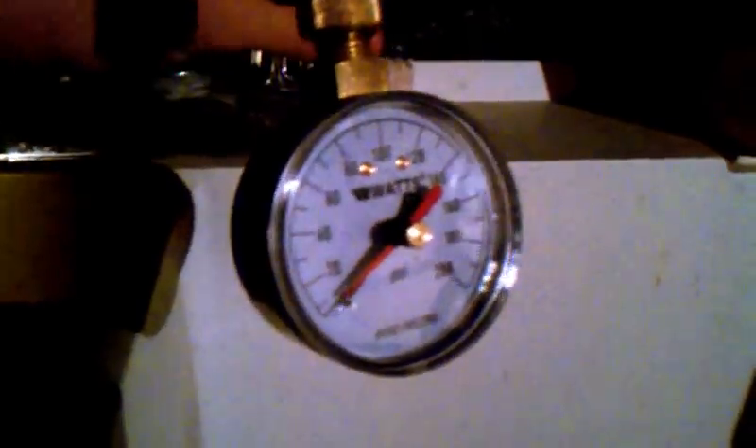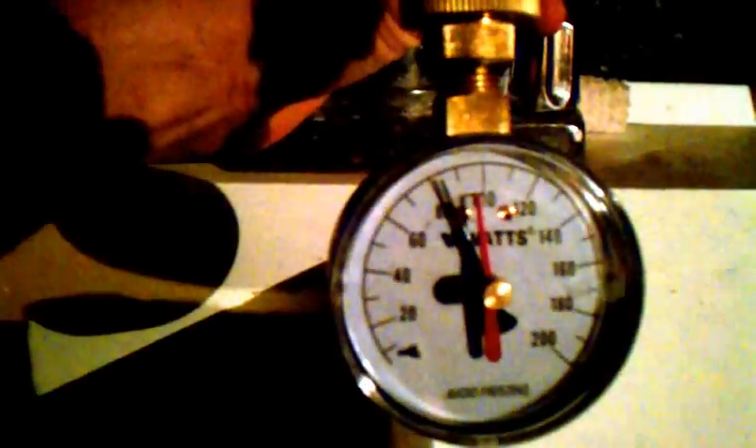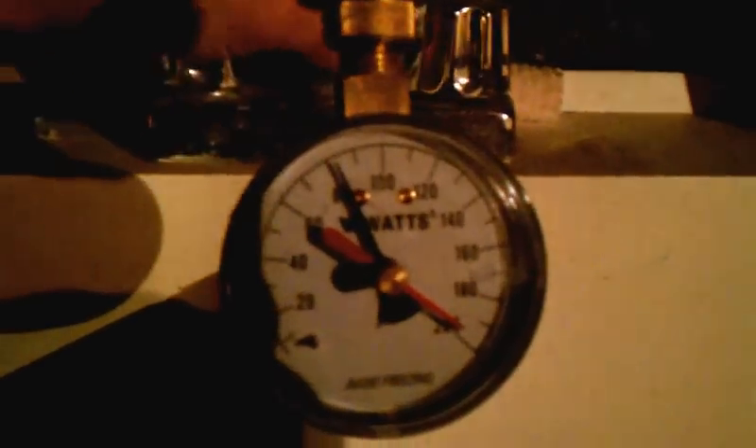So let's take a look. I got it screwed on and I got a little red indicator. We'll turn it on right there. I don't know if you can see that, but it is right now sitting at 80. The little indicator jumped up — it's not a glycerin-filled meter or anything, but it's 80. That's pretty high and unfortunately we need to fix that.